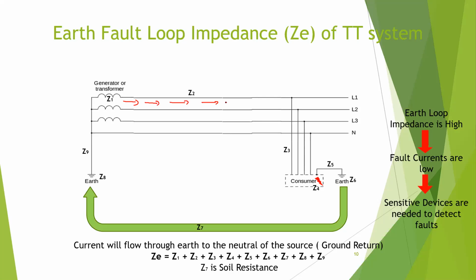So your fault current will flow through this path, and from the inside it will go here and touch your enclosure, and from the enclosure it will go through the earth rod to earth and come back to the earth rod of your source side. So this is the earth loop. See, this is a loop. This is neutral, and in a three-phase supply, let's assume this is a star. Now this point is N, this point is Earth. That is the connection I have indicated here. So this is the path you have for your fault current. The resistance of this path is called the earth loop impedance.